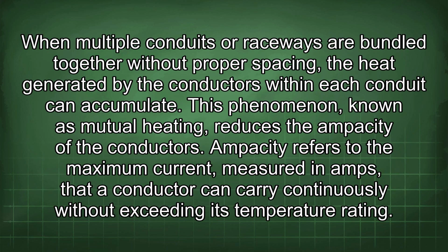When multiple conduits or raceways are bundled together without proper spacing, the heat generated by the conductors within each conduit can accumulate. This phenomenon, known as mutual heating, reduces the ampacity of the conductors. Ampacity refers to the maximum current, measured in amps, that a conductor can carry continuously without exceeding its temperature rating.